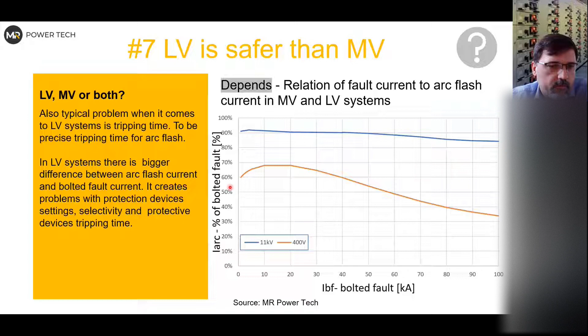So we have a short circuit current, which is 100%, the arc flash current is 95%, and our protection device sees more or less the same current and can trip in more or less the same time. For the low voltage system, it's a little different because it can go down to 37%. So if you have 100,000 amps for the normal short circuit current, for the arc flash it might be 37,000 amps, and your protective device will see a smaller current and will not trip in 100 milliseconds. It might trip in 2 seconds. So this is generally a problem for low voltage systems and arc flash.